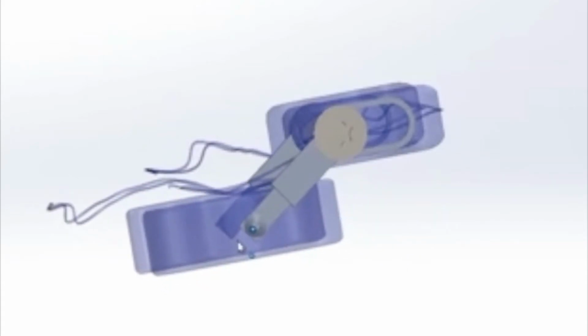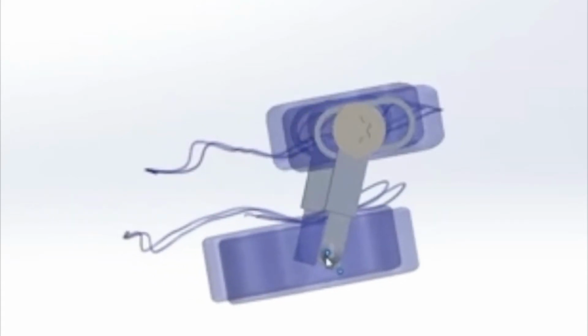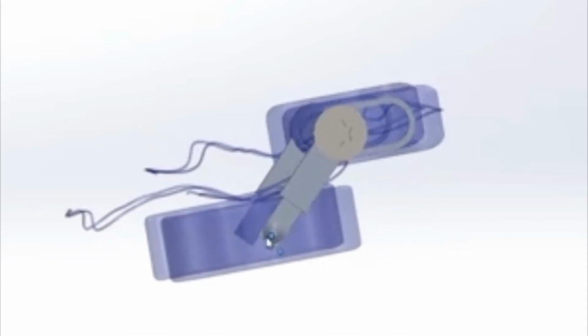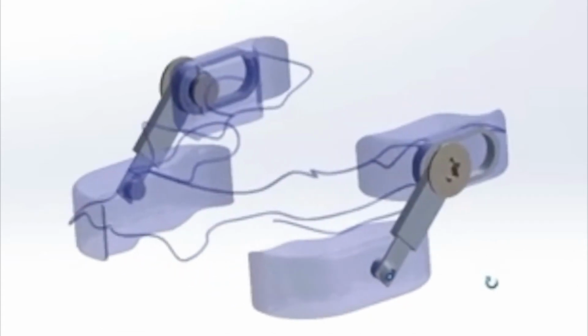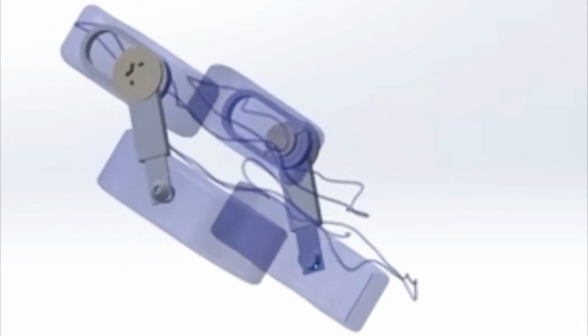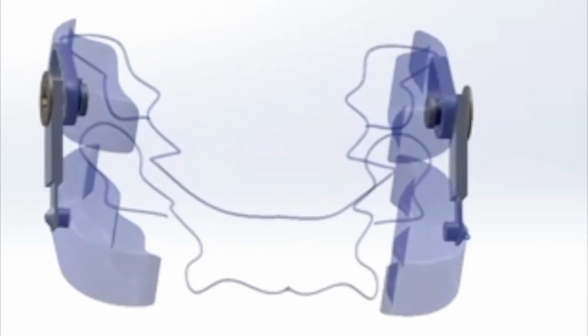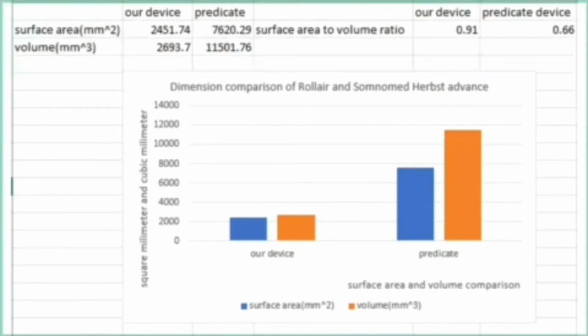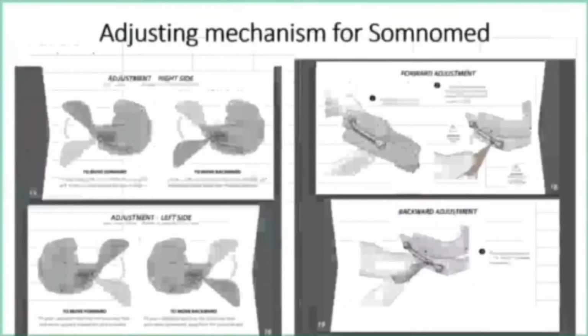For safety concerns, we minimized the risk of hurting users by filling in the edges of all components and deleting detachable parts. We also changed the side tubes from a circular shape to a rectangular shape, so the tubes are less likely to touch the mouth. Compared to the predicate device, RollAir has 1/3 of surface area and 1/4 of the volume reduced. Moreover, the surface area to volume ratio is 0.91 for the RollAir compared to 0.66 of the predicate device. Adjusting RollAir only takes 3 steps, whereas for the Herbst Advance, it takes a special tool and it is more complicated to make adjustments.